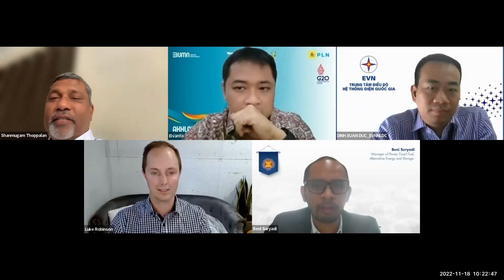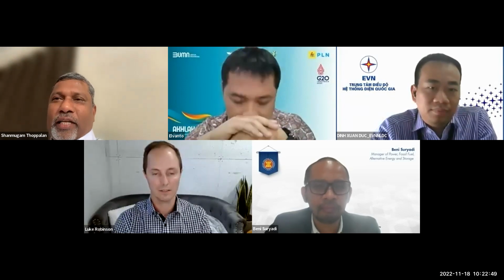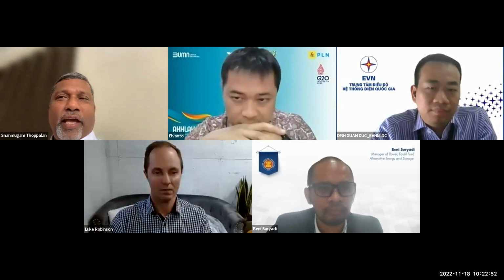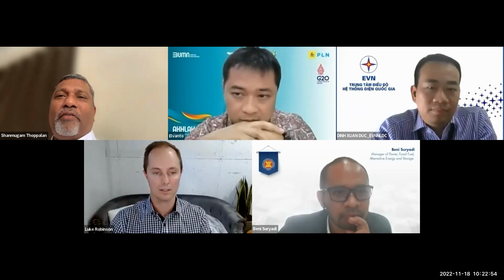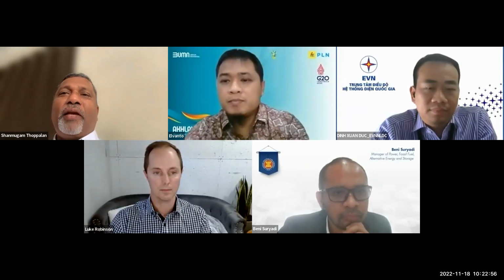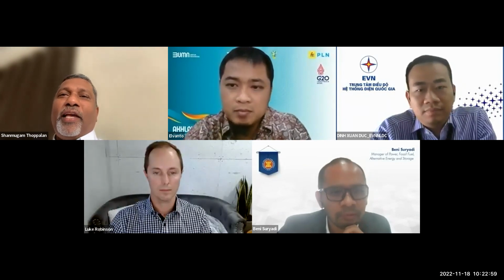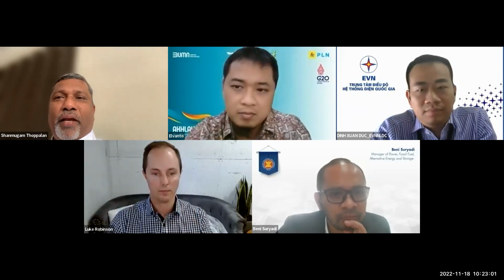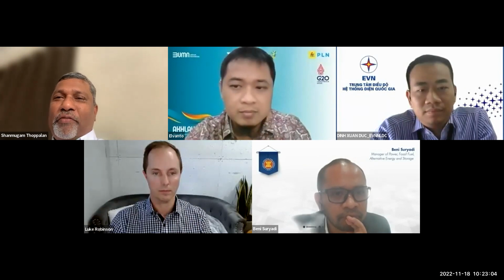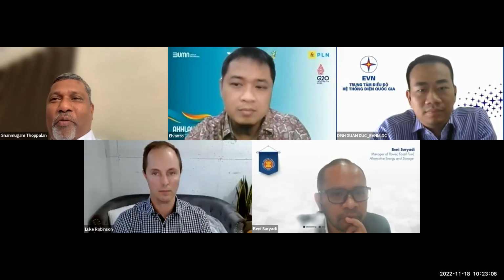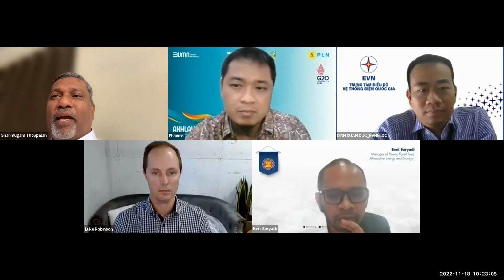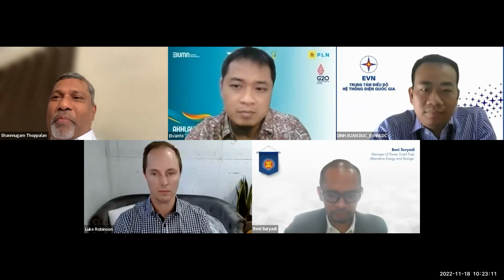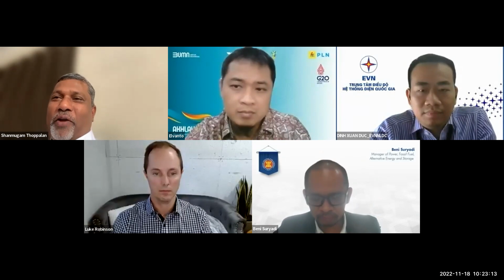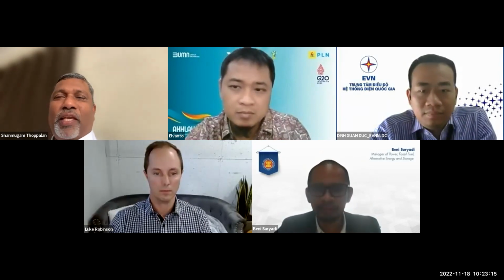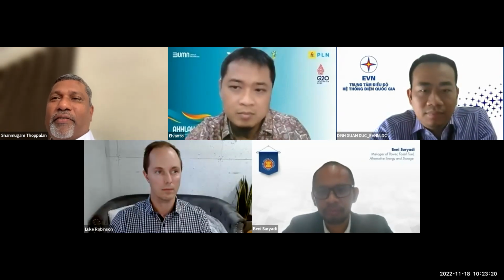Maybe I can start. Yes, definitely, because contingency reserve is only for contingency, but with the high level of intermittency, secondary reserve becomes more important than before. It has to cover regulation, intermittency, and ramping situations. Quite interesting from Mr. Ding's slide, I see he's increasing the secondary reserve from 900 to 1,700. Mr. Ding, how do we strategize this increase, and is it cost effective? How do you manage that increase in secondary reserve?